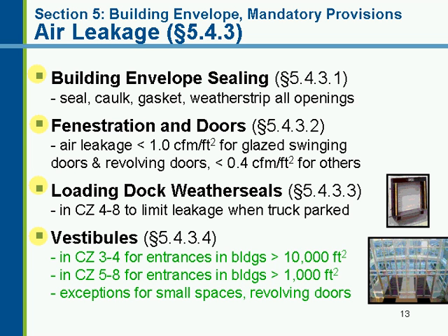So if you're in a very cold climate and you decide you want to put in some baseboard heat or something within the vestibule itself, then the outside door is considered part of the building envelope, and that would need to comply with whatever the fenestration requirements are. If you have another situation where you do not install any heating or cooling within the vestibule itself, then the interior and exterior of the unconditioned vestibule shall comply with the requirements for a semi-heated space. So that's the difference there.